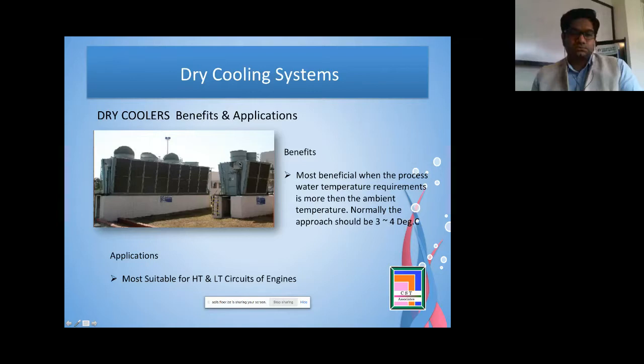And the second is the jacket water temperature. Jacket water temperature is basically where all the pistons and other things are moving. And the temperature of that jacket has to be something like 80, 85 or 90 degrees centigrade, again depending on the manufacturer and this one. So there is no need for an adiabatic application on these kinds of coolers.